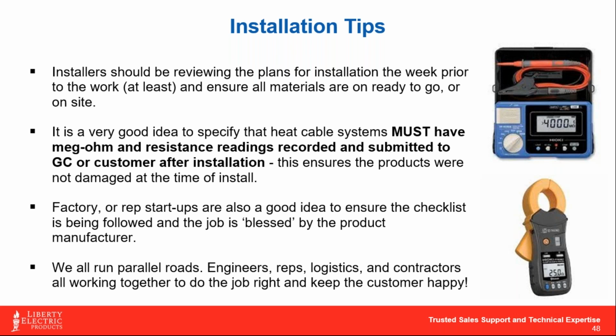Just don't walk on the cables, don't drive a concrete buggy on them, don't hit them with metal tools, and you should be fine. The big thing is continually checking that cable with the megger tester before, during, and after installation. It also coincides directly with your warranty—you'll need to submit your megger readings and resistance readings at the end of the job to qualify for the product warranty, no matter who the manufacturer is. It's probably the most important part of any of these installation tips.